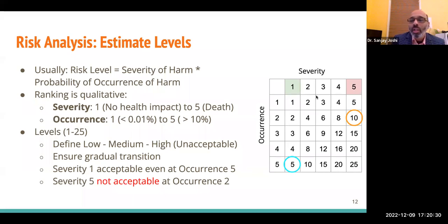So those are the columns along the severity. Then there are rows, the occurrence. Usually the lowest occurrence is less than a certain percent, and here I just chose 0.01%. Keep in mind, the standard says the risk is always there. The occurrence is never zero. And the highest typically is, if it happens more than 10% of the time, it's usually a 5.